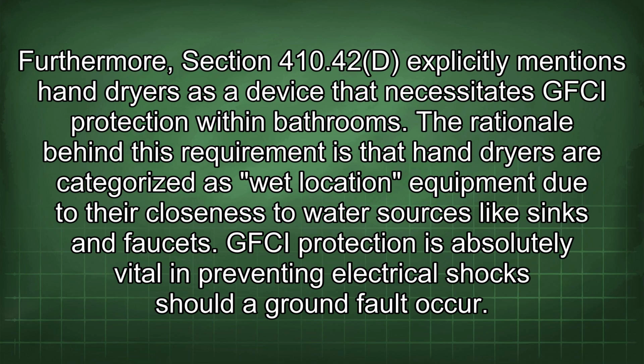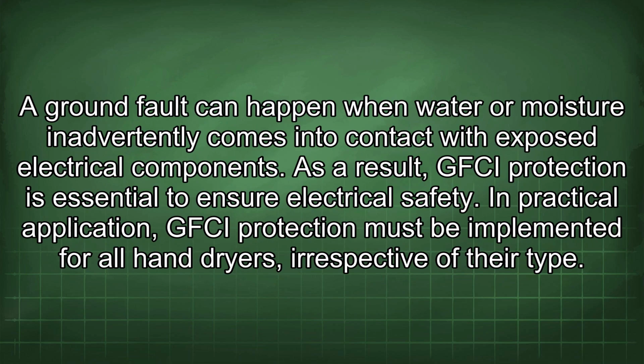The rationale behind this requirement is that hand dryers are categorized as wet location equipment due to their closeness to water sources like sinks and faucets. GFCI protection is absolutely vital in preventing electrical shock should a ground fault occur. A ground fault can happen when water or moisture inadvertently comes into contact with exposed electrical components. As a result, GFCI protection is essential to ensure electrical safety.